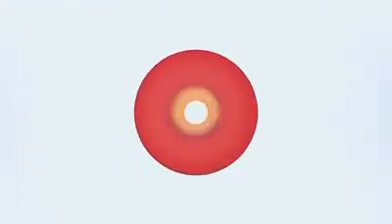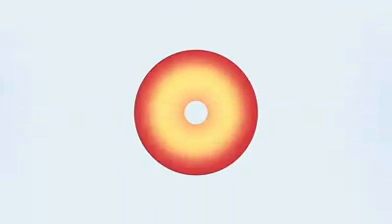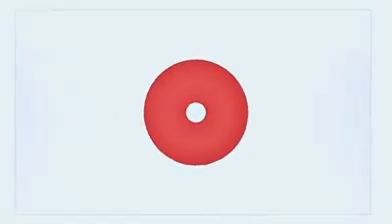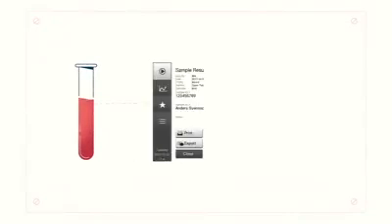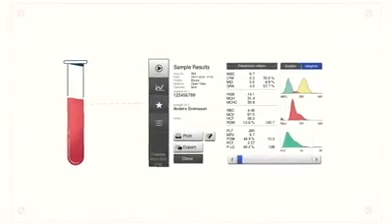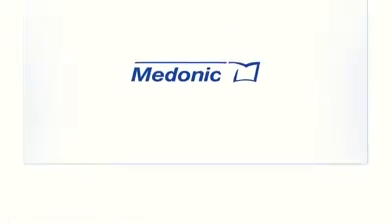A high voltage burning of the orifice will automatically be carried out only when needed, all to reduce wear and tear. In the end, you're presented with clear histograms and accurate values for the different parameters, all within a minute.